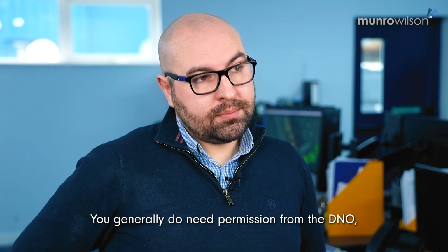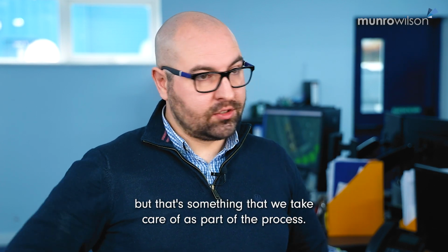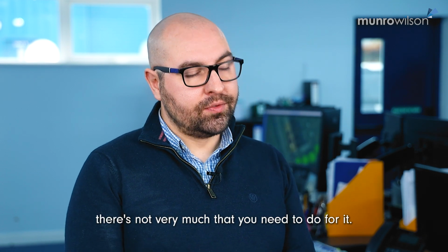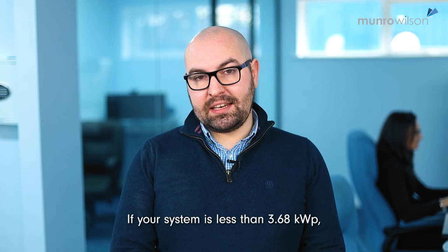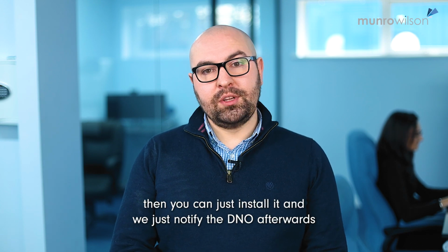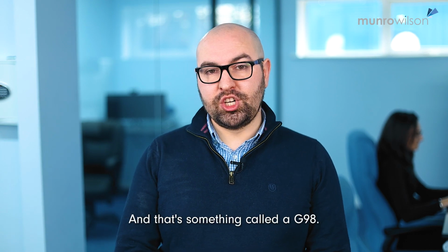You generally do need permission from the DNO, but that's something that we take care of as part of the process. So other than signing a couple of documents, there's not very much that you need to do for it. There are different levels of permission. If your system is less than 3.68 kilowatt peak, then you can just install it, and we just notify the DNO afterwards that we've done so, and that's something called a G98.